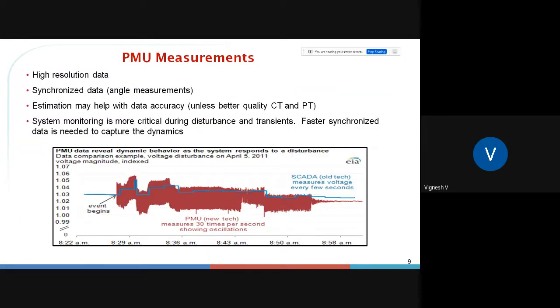Let's see the typical differences between PMU and SCADA data. The red line is PMU data, giving 30 frames per second, and it clearly shows oscillations, whereas the blue line is SCADA data, which does not convey anything about the oscillation. This shows how the high refresh rate of PMU helps us visualize the grid better.